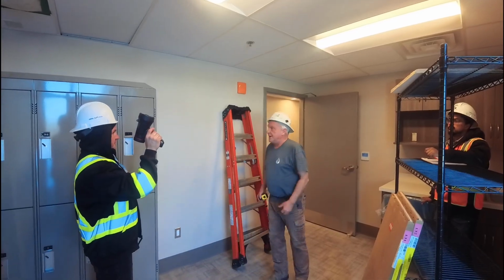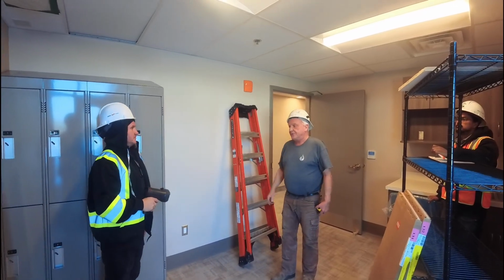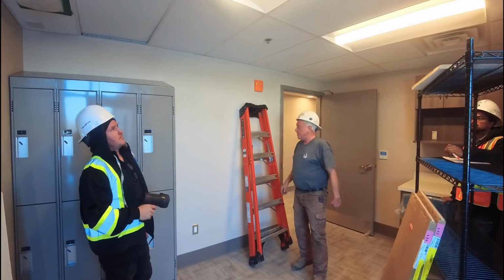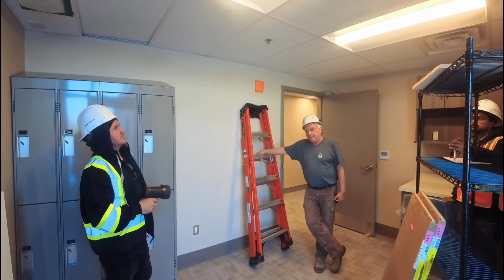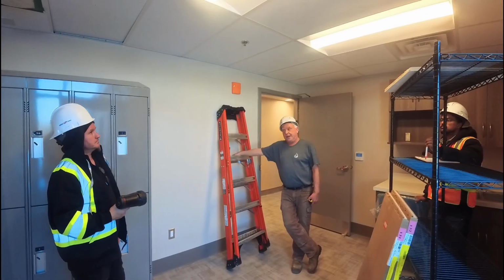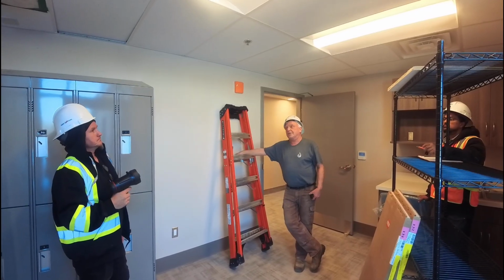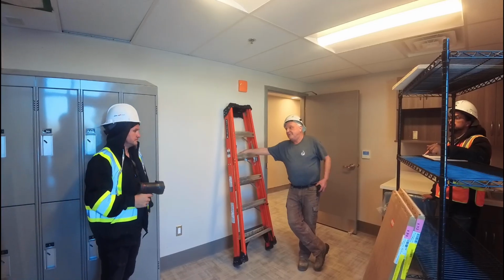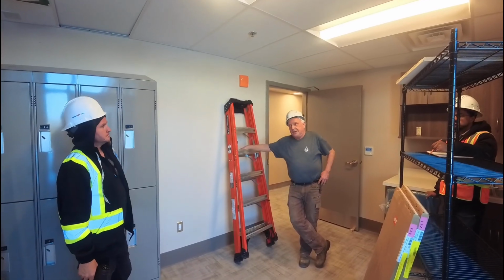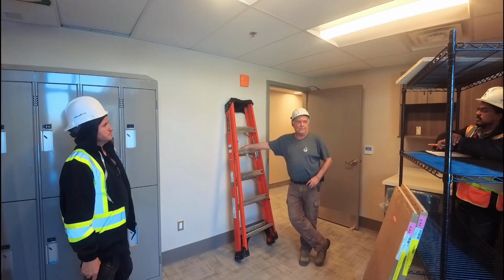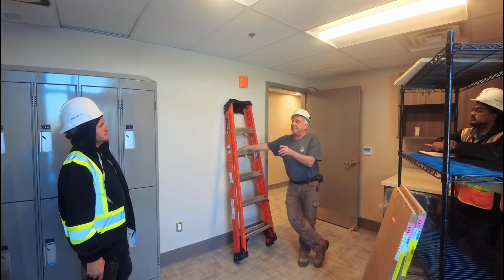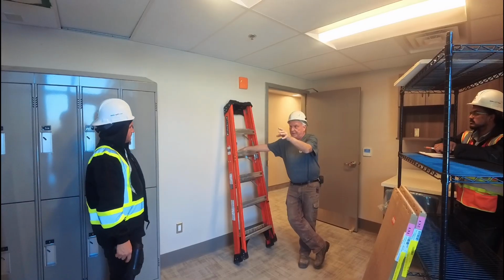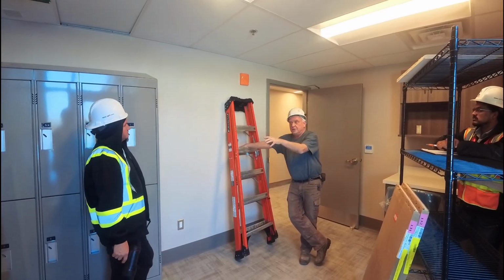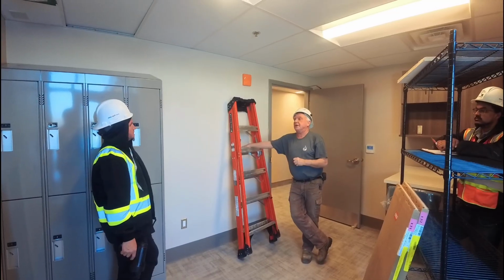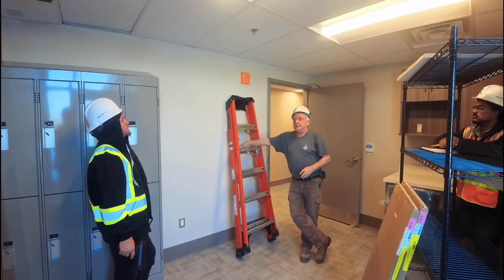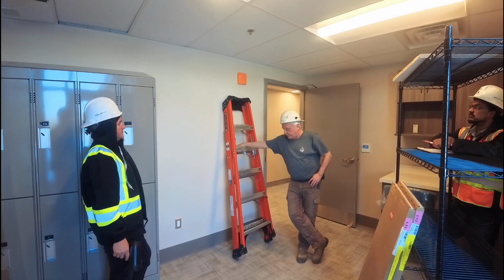There'll be 4 filters in this area too? That's correct. There's a fan coil directly above. There's always 4 in each unit. Two on the supply end, 2 on the return end. Right. Once again, MERV 13 on the return end, and MERV 10, or it actually calls for MERV 8, but the first shipment I think we got MERV 10s, because that's what was easily available. But now the second shipment, the one that I have, I have over 700 filters in that C-can out there for you as your replacement filters. They are actually MERV 8s, I believe. They got the right MERV number on those ones.